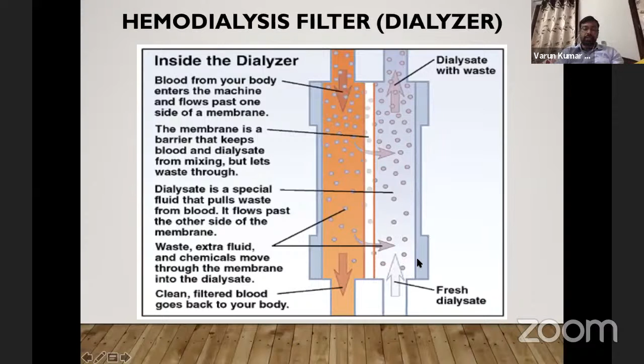Now here, once it starts coming down, the creatinine concentration of blood comes down because it has already diffused. And here the dialysate that has entered does not have any creatinine at all. Suppose this has a creatinine of 0 and this has a creatinine of 2, there is still some diffusion happening. Here creatinine is 10, here it becomes 5, from 10 to 5. Here creatinine comes down to 2. But in fresh dialysate, creatinine is 0. So even if the creatinine concentration is very minimal, still diffusion happens. That's why we use the opposite direction. It's called counter current.